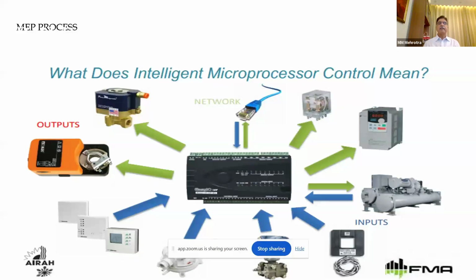Now building management system will have some microprocessor based control. There is a word called Internet of Things, IoT. IoT is where you have actuators and sensors. They collect the status of the facility and provide an electrical signal, be it a compressor in air conditioning plant, be it fire alarm system, or status of electric circuit breaker, or a computer system. Now, all these signals are getting connected to my BMS. BMS has got a microprocessor in the heart of it. So, it will make sure that your communication with these facilities is complete.